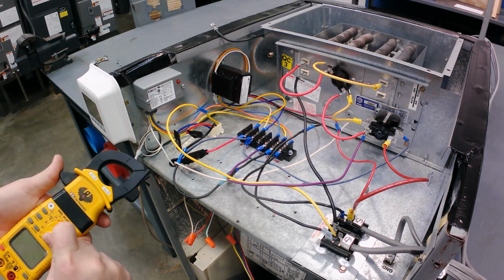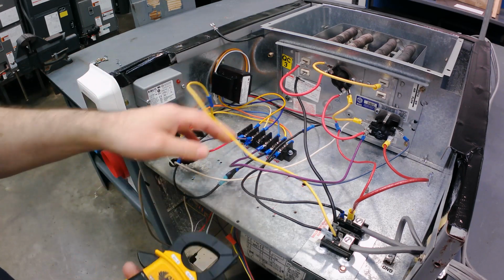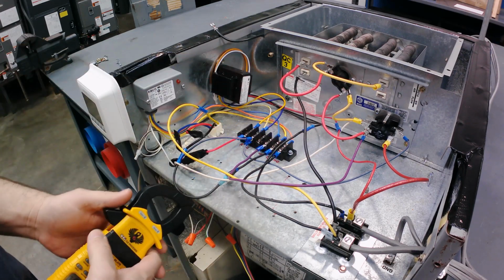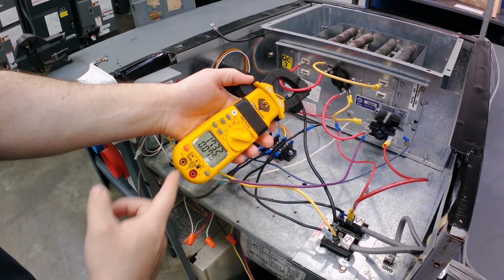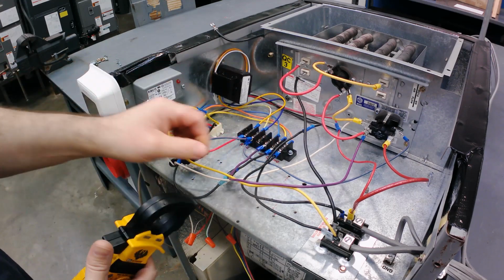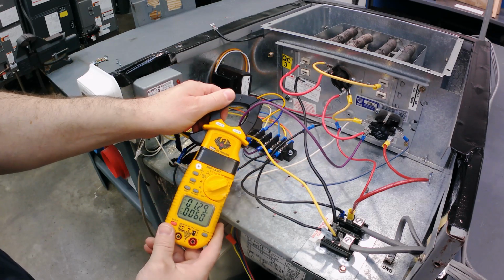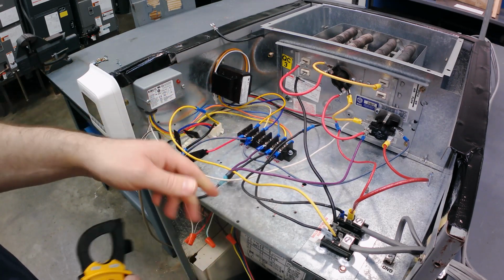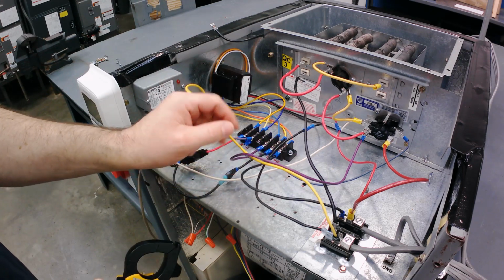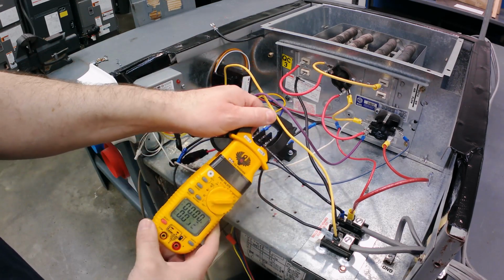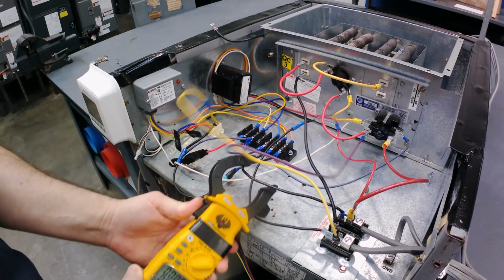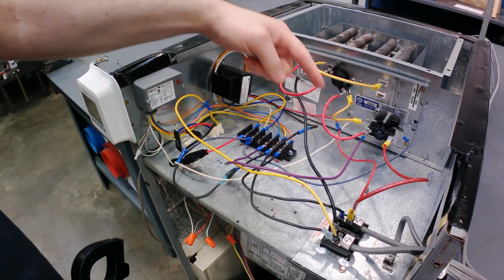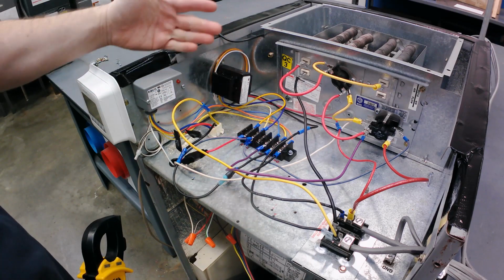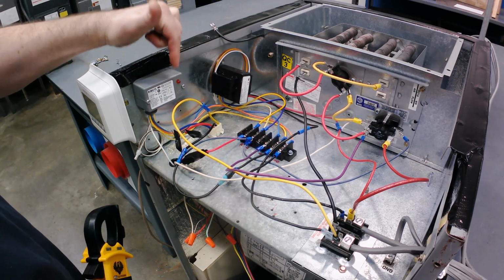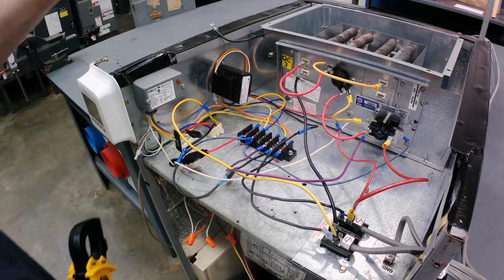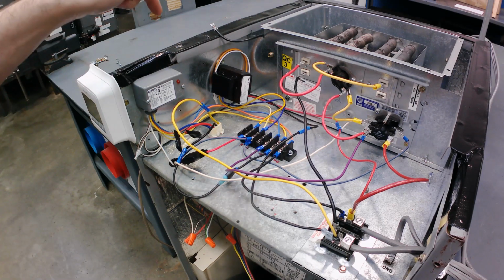My fan is on. Because we're using this normally closed circuit, I've got one heat strip on, 17 amps, and I've got my fan on as well, and that's pulling 1.3. So there's no amperage on the normally open because we're not using that switch right now. So power's going through the normally closed switch to turn on our fan, and that rib relay has nothing to do with it right now. So it's a 9340 in a different version.